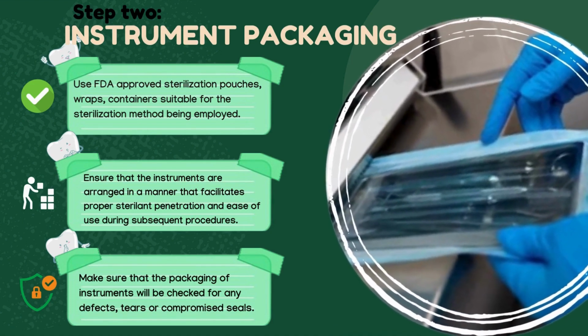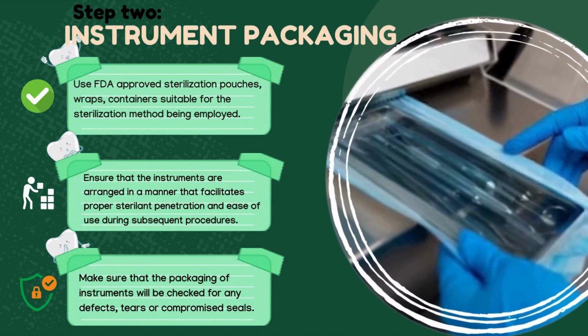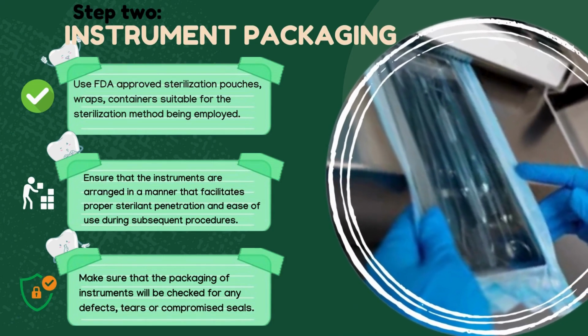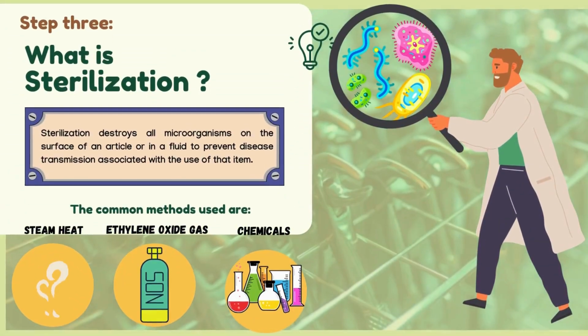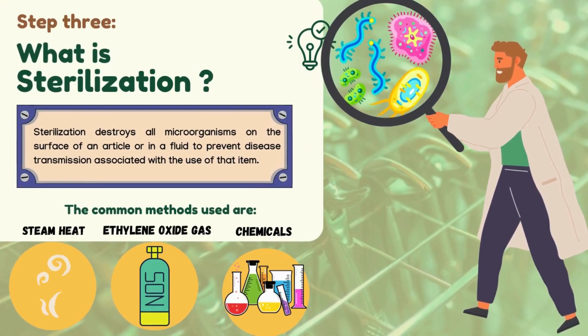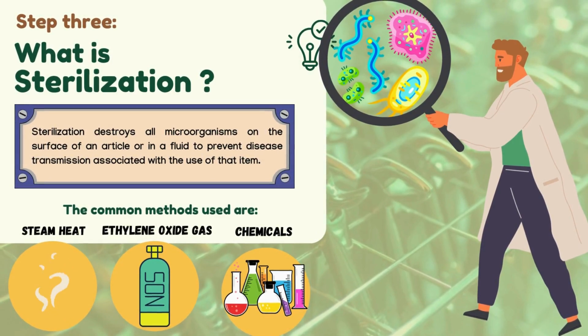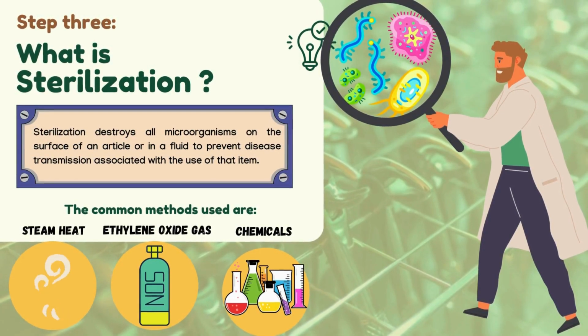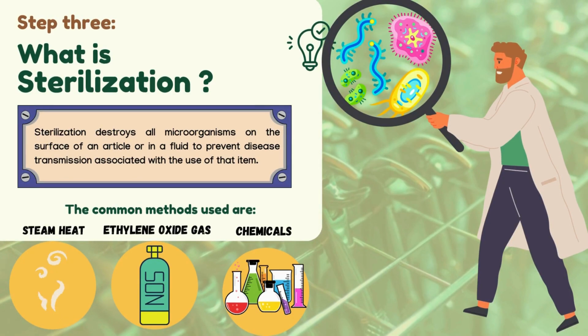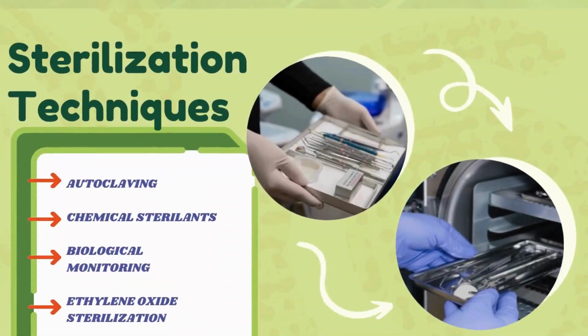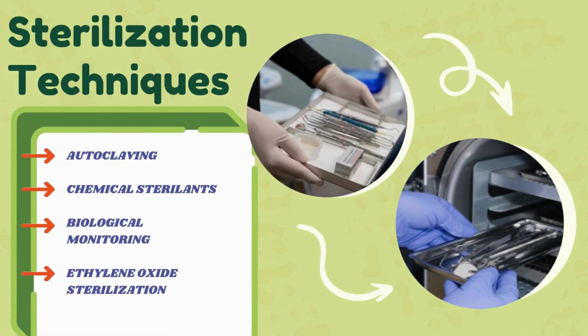After instrument packaging comes the crucial part of making sure that there will be no cross-contamination, and that is sterilization. So what is sterilization? It destroys all microorganisms on the surface of an article or in a fluid to prevent disease transmission associated with the use of that item. The common methods used are steam heat, ethylene oxide gas, or chemicals. Here are different techniques of sterilization.